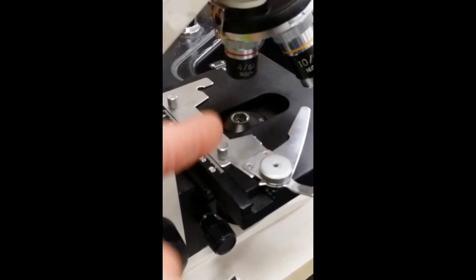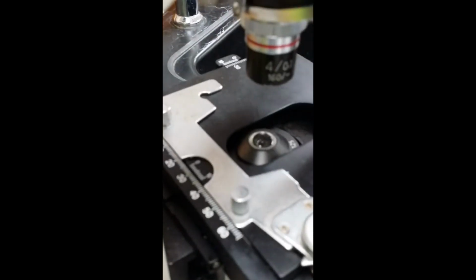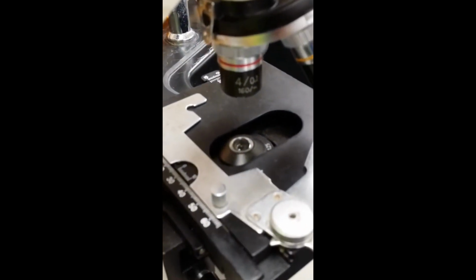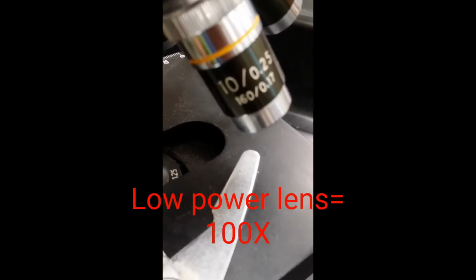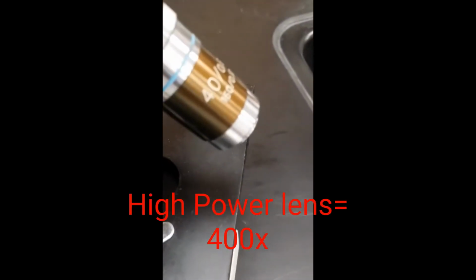A basic review of microscope use. So the microscope should always be stored with the stage all the way down and the dissecting lens, which says 4 on it for a total magnification of 40. The low power says 10 for a total magnification of 100 because the eyepiece is 10. And then high power says 40 on it for a total magnification of 400. Never use the coarse adjustment when you have the high power in place.